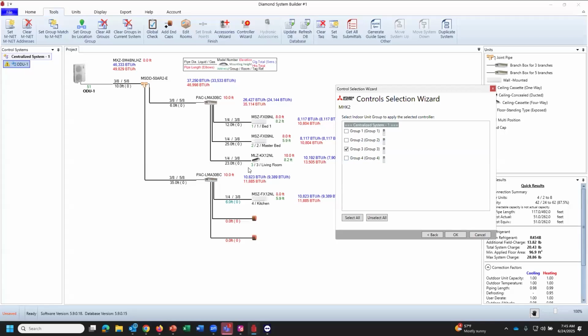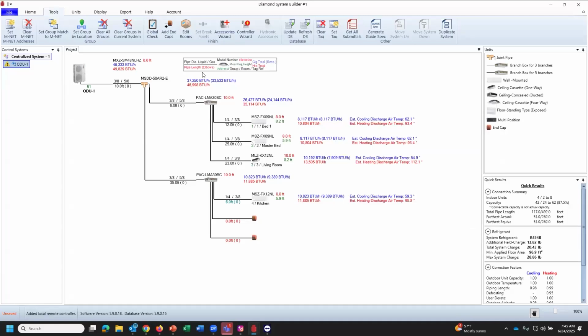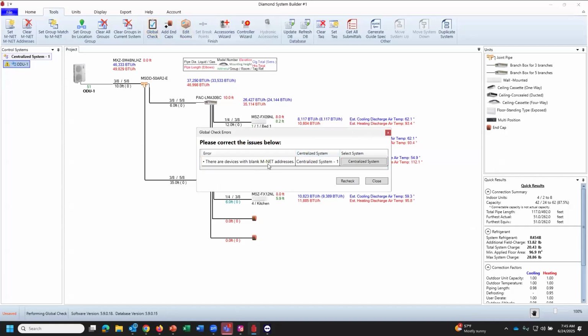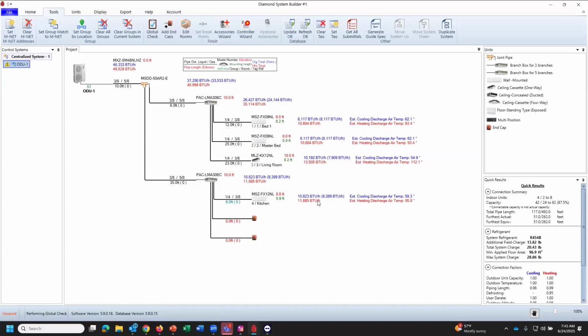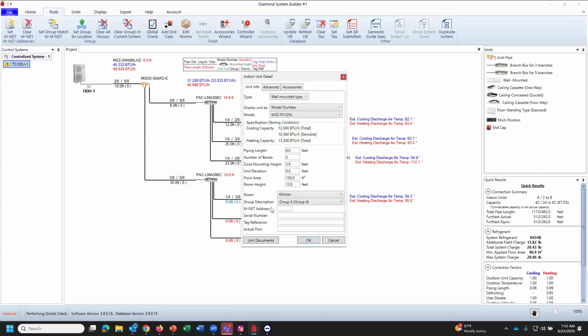So we're going to have this group 3 over here, and we're going to go ahead and add an MHK2 to that one. And I missed an M-NET address in here somewhere, so we can go back in here and double check that. The second number right here is what you assign as an M-NET address, and I missed it right here, so my M-NET address here is going to be 4.